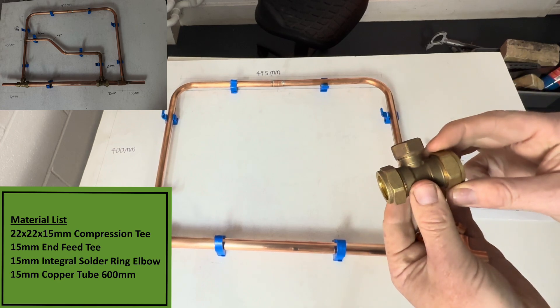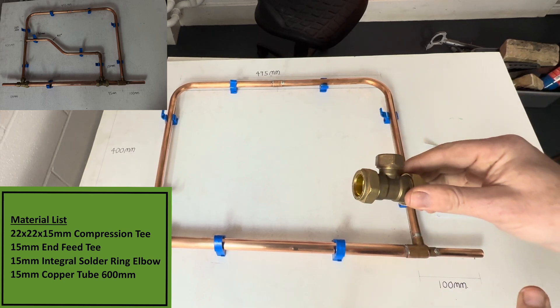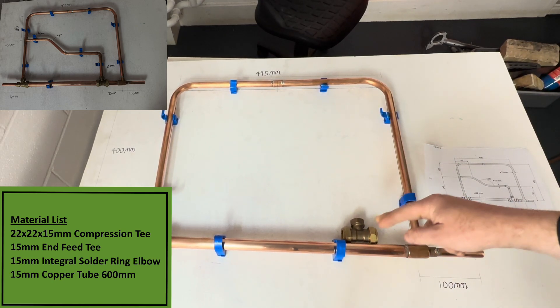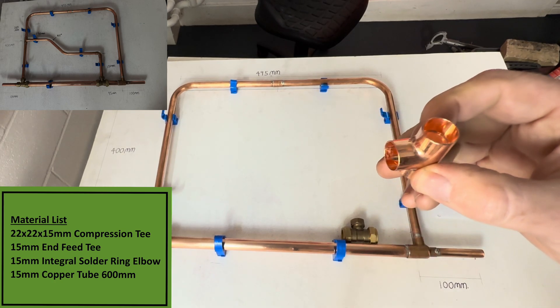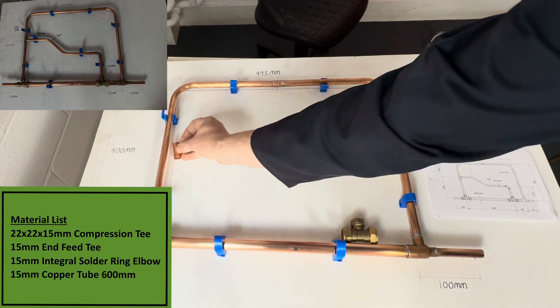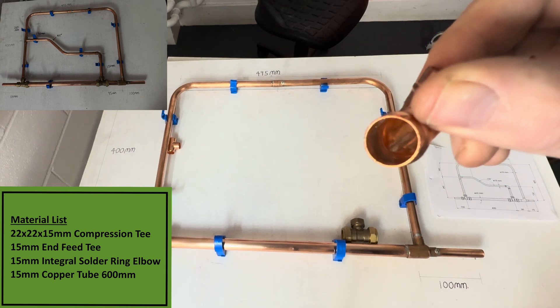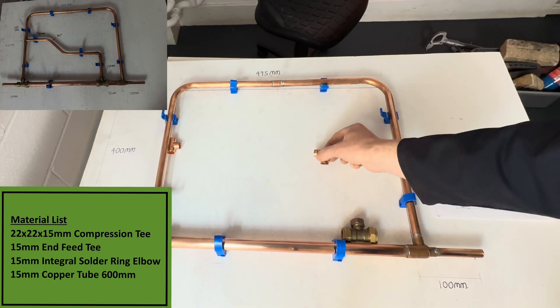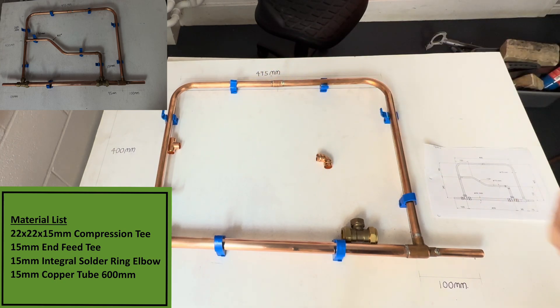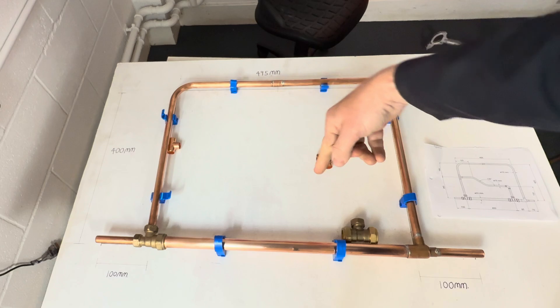The fittings we need for this are a 22mm x 15mm compression T, which is going to go somewhere here on the modification. Then we've got a 15mm End Feed Tee which we are going to solder, and that's going to go somewhere here. We've also got a 15mm integral ring fitting — this is where the solder is already built into the fitting — and that's going to go somewhere here like this. Because we want to be accurate, we're going to draw in the modification first.